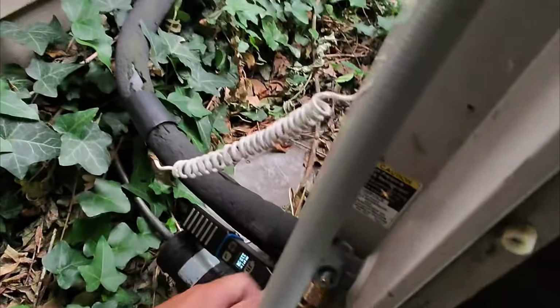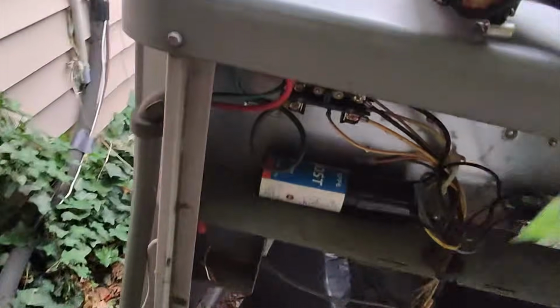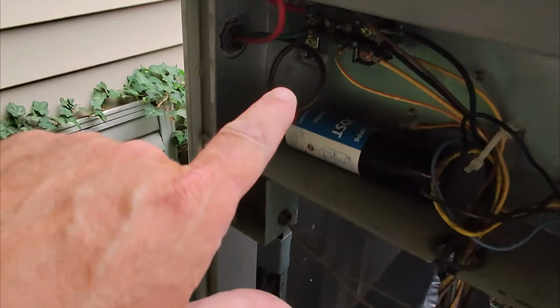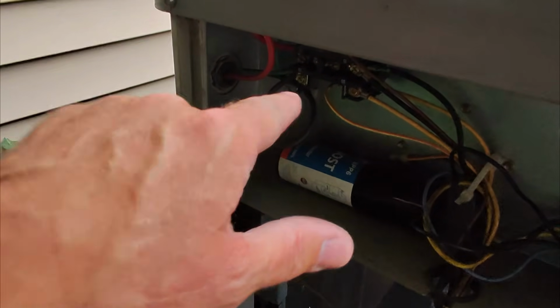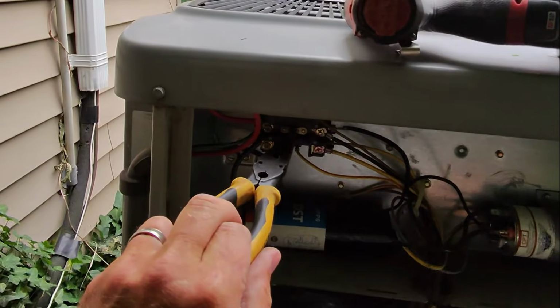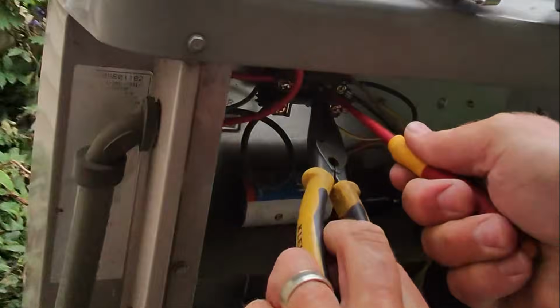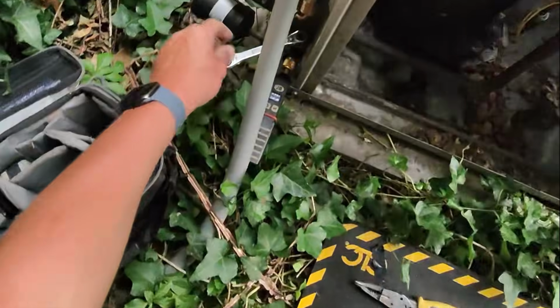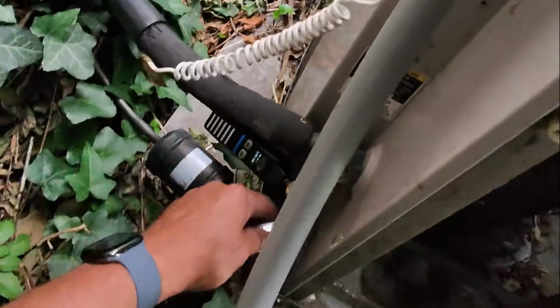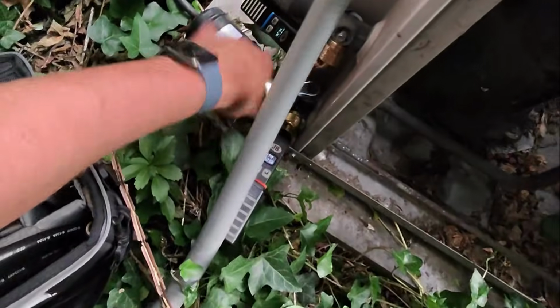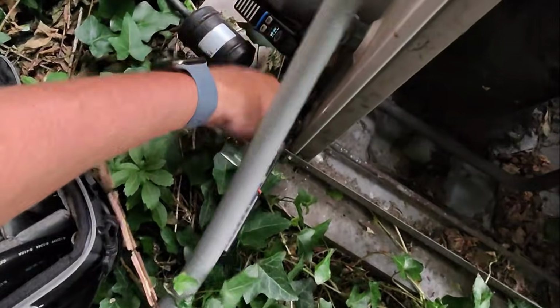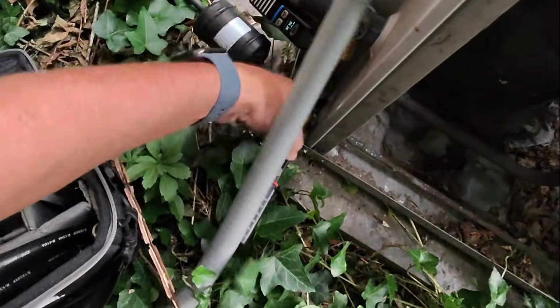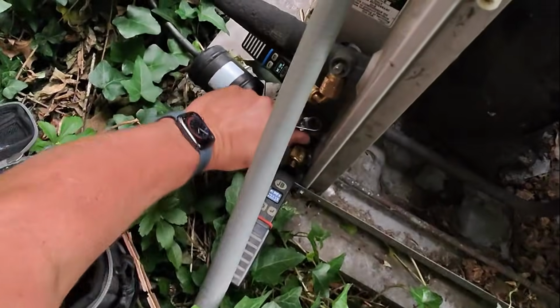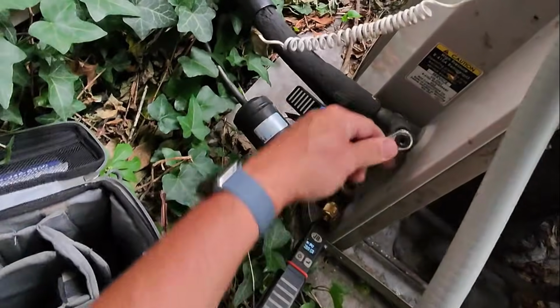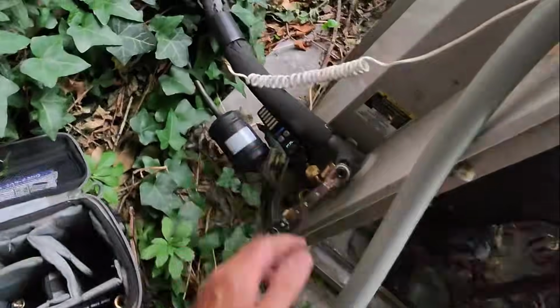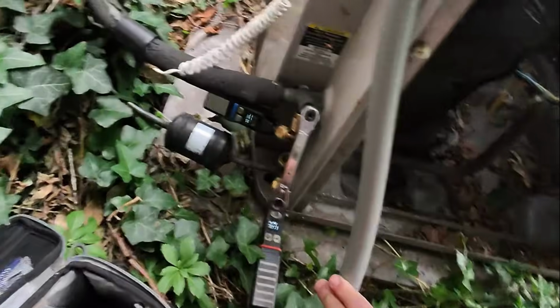Let's crack that one as well. Okay, now let's get an insulated screwdriver, and we're going to shove close the contactor. Okay, let's push that in there. Beautiful. Okay. We're going to close this valve here. This is the liquid line. Okay, that's fully closed. Now we're going to get our service valve ready for the suction side. That's going to drop down.